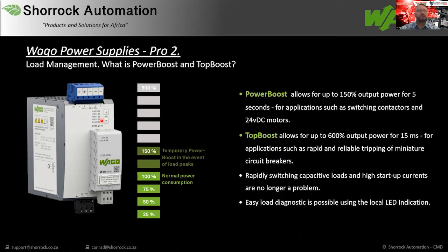Now, the reason why I would also like to highlight this is we need to understand that even though I mentioned that we have a 96.1% efficiency on our WAGO Pro 2 40 amp power supply, if you run that power supply at 75% of its full load, you will actually be able to... Efficiency is also linked to how far you are into your full load. The values I've been giving at 96.1% is linked to running at full 100% of your load.